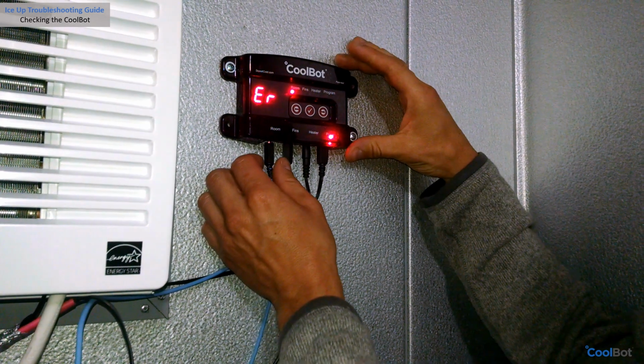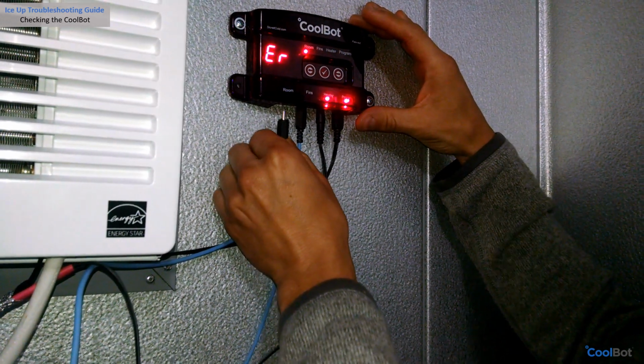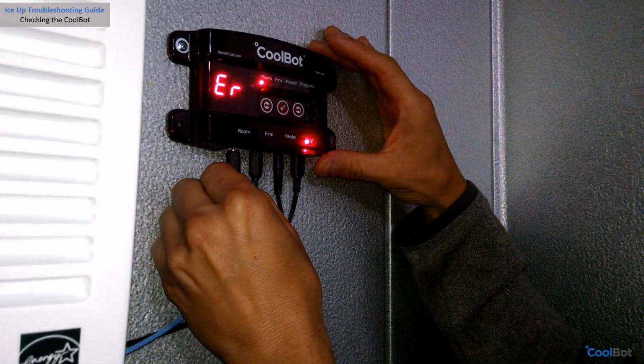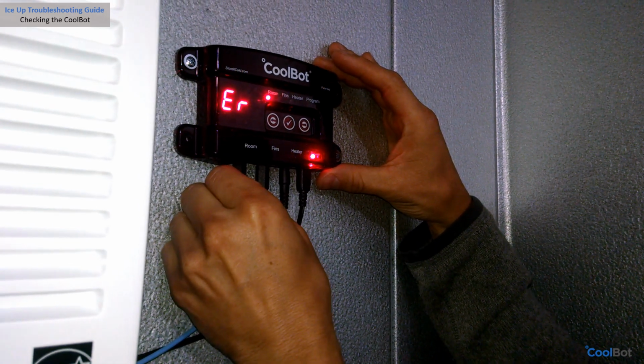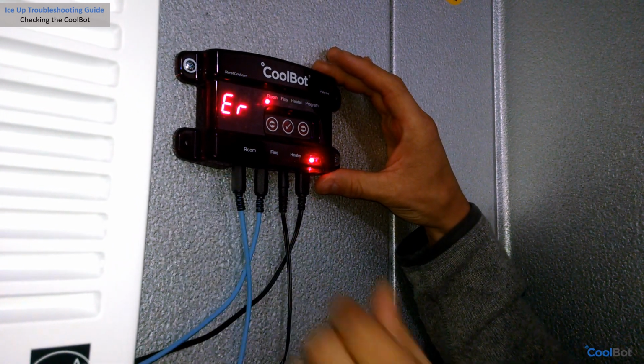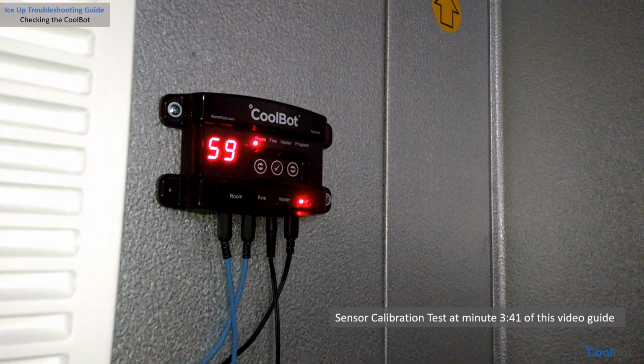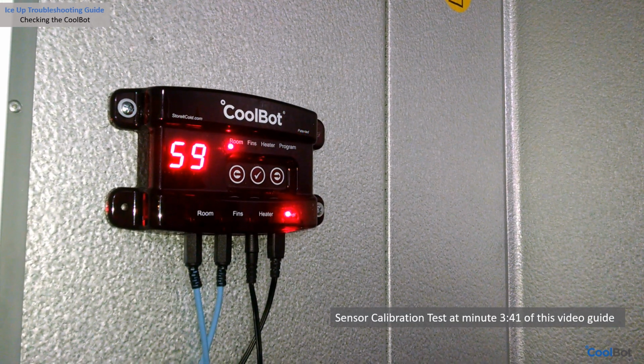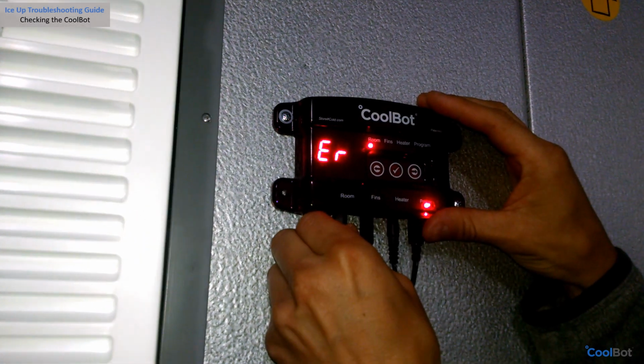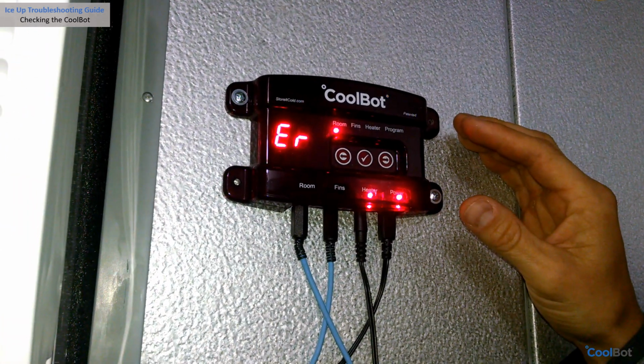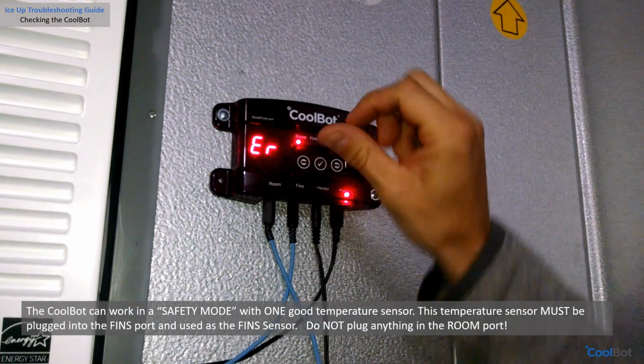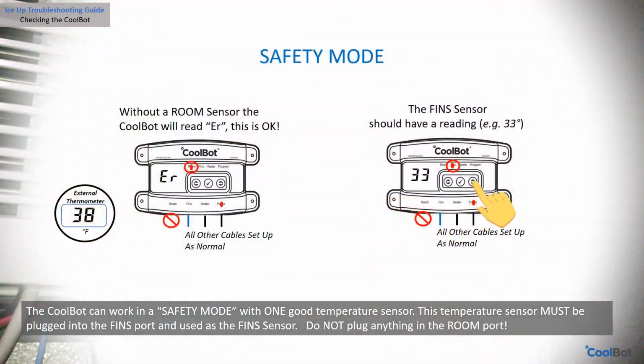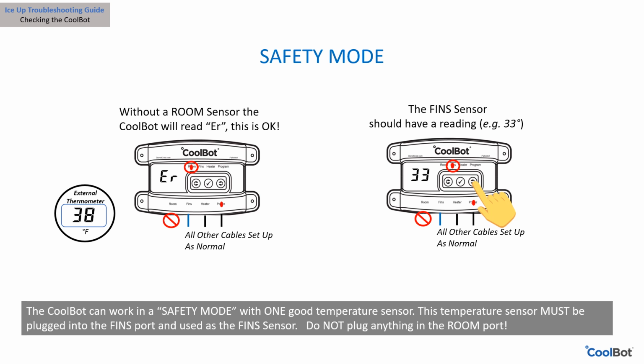Is the CoolBot displaying a permanent ER message? If there is an ER message on the screen, unplug the room sensor and firmly plug it back 2 or 3 times into the port. If the ER message clears, proceed to perform the sensor's calibration test from this guide. If the ER message persists, unplug the sensor and discard it. Leave the CoolBot without a sensor plugged into the room port. The ER message will display permanently until a new sensor is installed in the room port. This is okay. Your CoolBot will be working on a safety mode in the meantime.